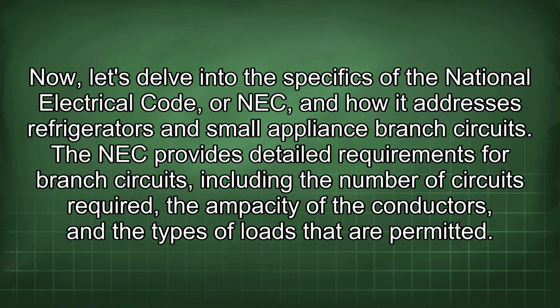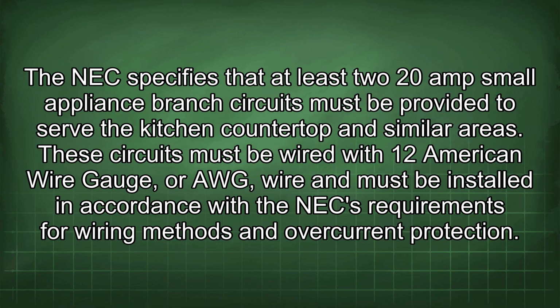Now let's delve into the specifics of the National Electrical Code, or NEC, and how it addresses refrigerators and small appliance branch circuits. The NEC provides detailed requirements for branch circuits, including the number of circuits required, the ampacity of the conductors, and the types of loads that are permitted. The NEC specifies that at least two 20-amp small appliance branch circuits must be provided to serve the kitchen countertop and similar areas. These circuits must be wired with 12 AWG wire and must be installed in accordance with the NEC requirements for wiring methods and overcurrent protection.